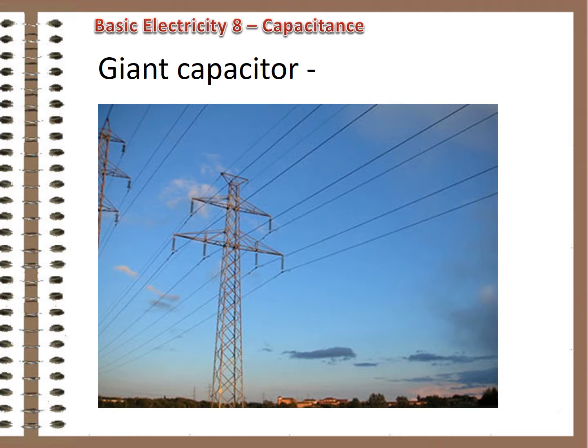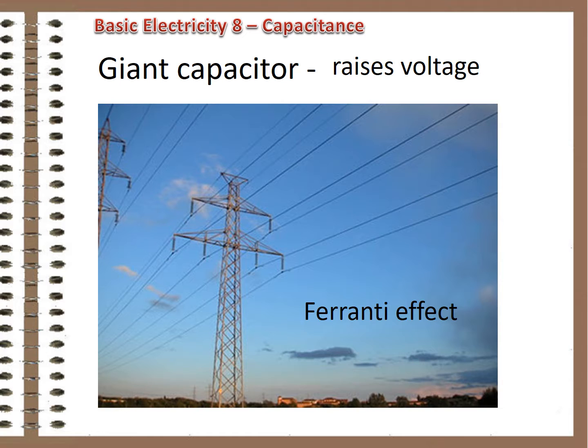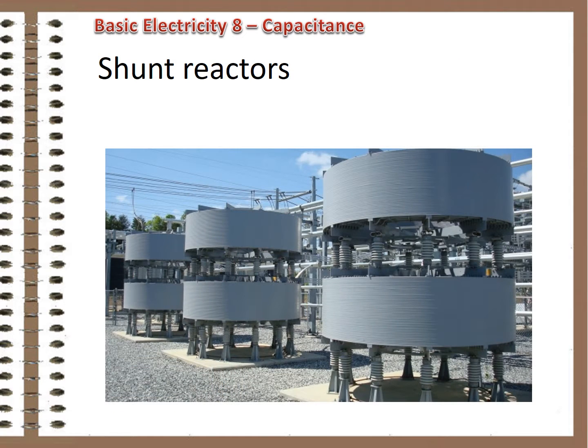If there is little or no inductive load in the circuit, the capacitive effect raises the circuit voltage. First noticed in underground 10,000 volt cables installed by Sebastian Ferranti in 1887, the Ferranti effect can cause a voltage rise of 10% or more between the sending and receiving ends of a transmission line. To counter this effect, shunt reactors are often placed at the end of the line expected to experience the rise, absorbing the capacitance and minimizing the voltage increase.